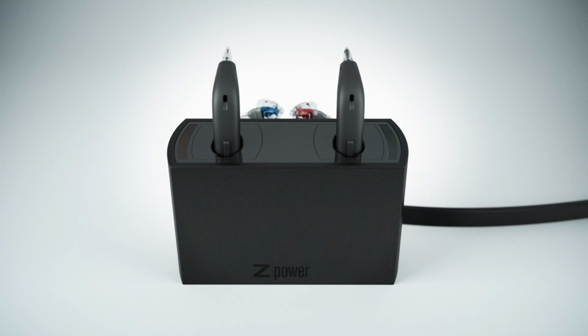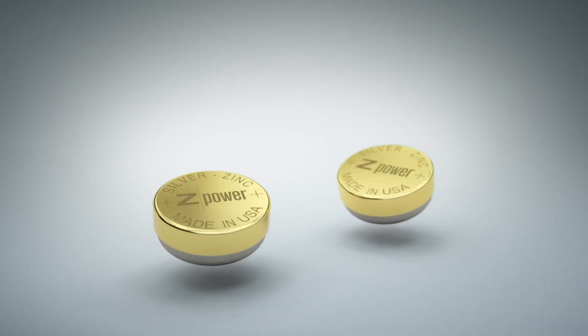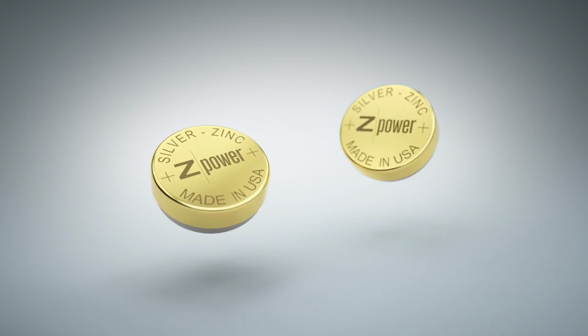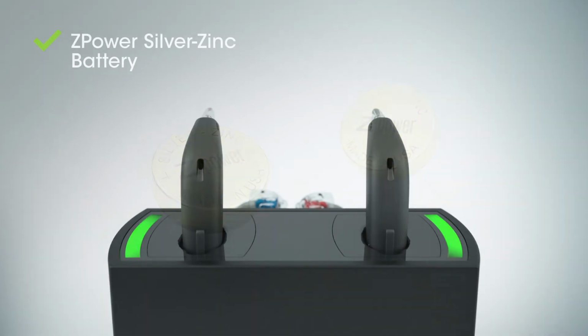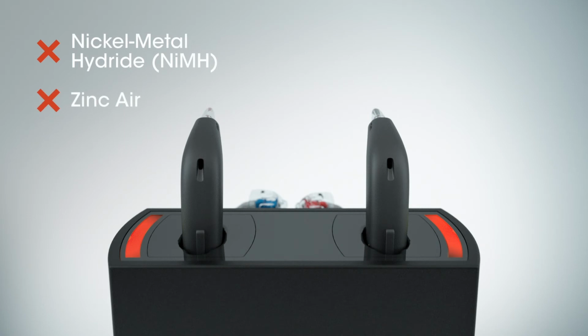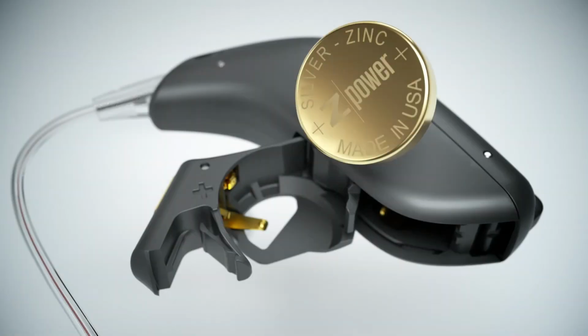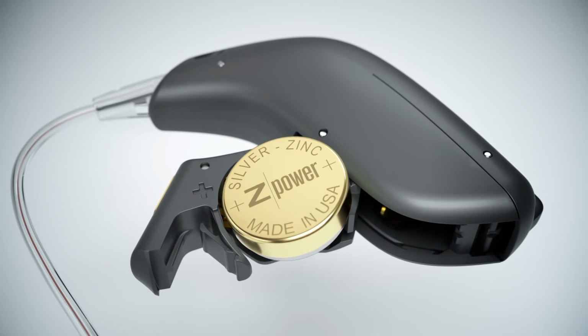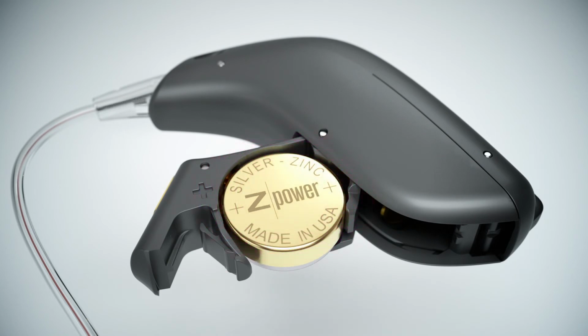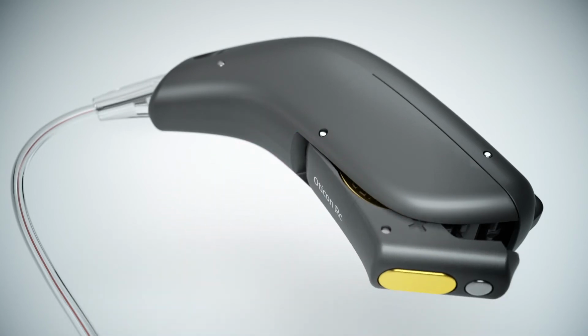If one or both lights are blinking red, please verify the hearing aid batteries are ZPower rechargeable batteries. You can see this written on the batteries themselves. Your charger will detect the chemistry of the battery and not charge them if they are the wrong chemistry. Replace the normal batteries with the rechargeable batteries and follow the normal process to charge your hearing aids.